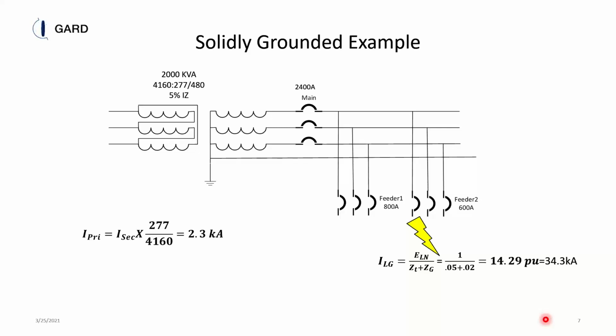But let's take a look at what happens on the primary of this. Once we have a ground fault on the secondary, more often than not, the primary circuit also trips because we're getting 2.3 kA on two of the phases of the primary to feed this current on the secondary. So chances are we're going to blow a couple of fuses over here because of a ground fault over here, and because we're feeding all this current to this transformer, we're going to get line voltage dips.